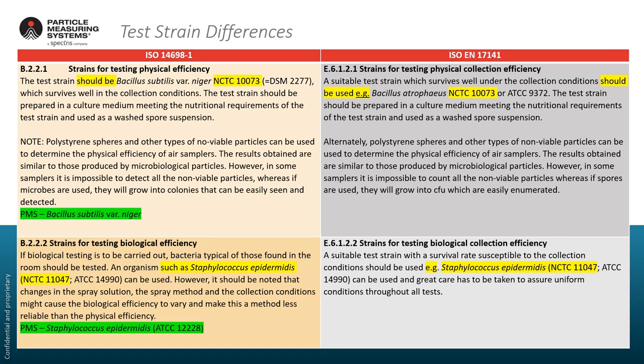The strains used for both tests are the same, with a little bit of language change — it should be Bacillus subtilis in one and Bacillus atrophaeus in the other, for example. The EN 17141 leaves a little wiggle room to pick something suitable that meets site requirements. In both instances, the test strains used by Particle Measuring Systems on our validation documents meet the specifications for both standards.